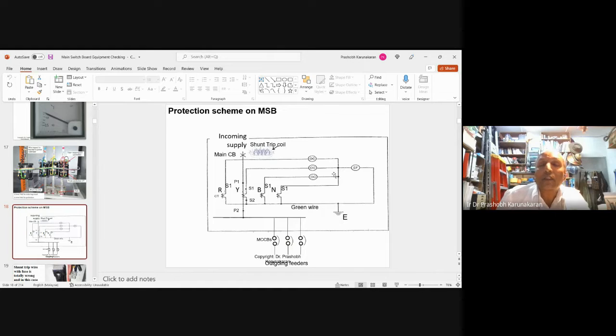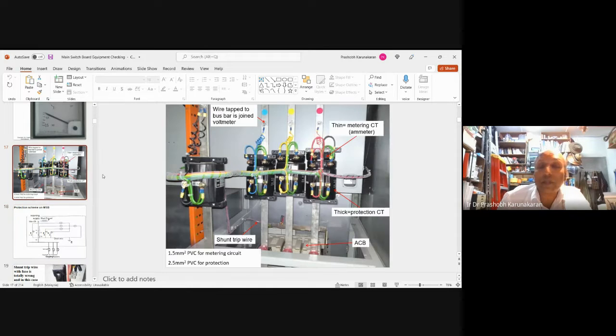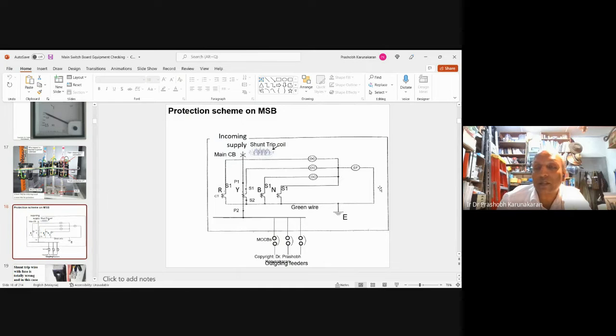By right, just like I showed you, if you put on all 4, the resultant will be 0 volts, 0 amps. So there'll be 0 here, and this 0 goes into the fault relay and comes out. Over here is all green wire - that's why I put green wire here, so you can see it from here. At all the other terminals, all green wire, coming out of this one.